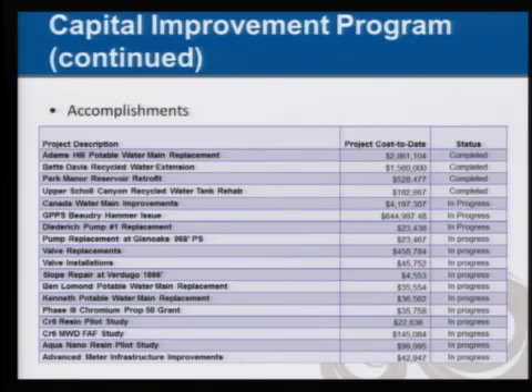Just for clarification, Gerald, sorry. Clarification: the hammer issue is basically a sudden pressure spike every time we turn the pump on, and that causes some water main breaks. So this project was to address what's causing that sudden pressure issue so that we do not face any water main breaks on the street.